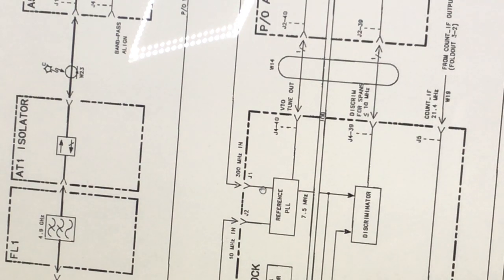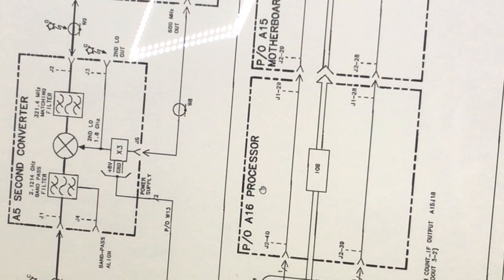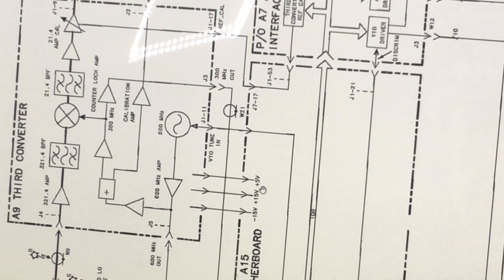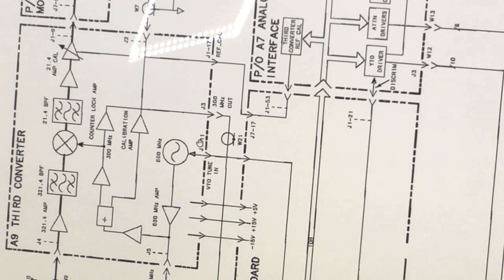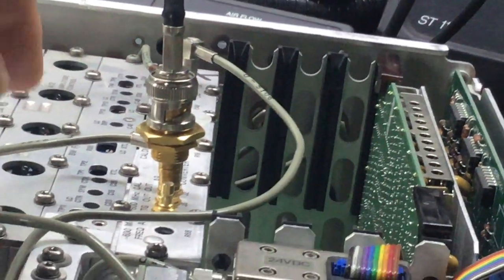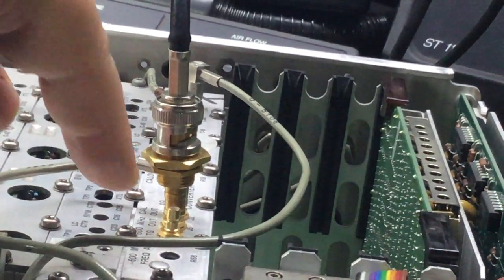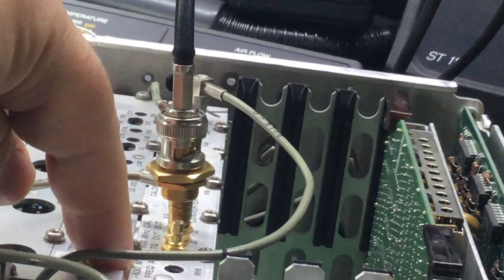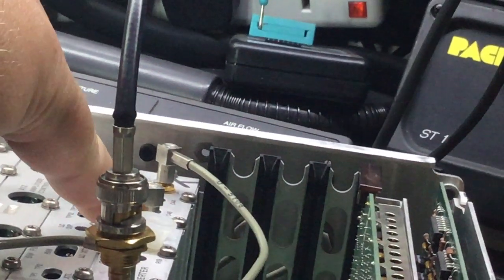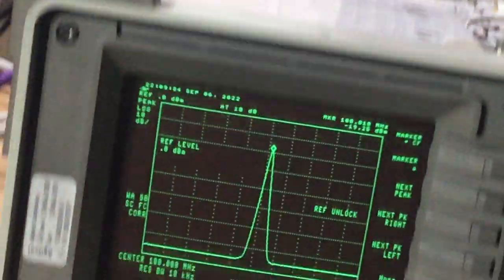We were struggling to get a bang on frequency of 300 megahertz. And so what I've done, I've just come back now to basics. Because off camera, there's some tuning that you can do on this module. There are some potentiometers just down here. It's very difficult to see at this camera angle, but there's one there for the frequency, the 600 megahertz coarse frequency adjustment. And then there's another one a bit further down here, which is for the actual level, the 300 megahertz level, which comes out of the calibrator.